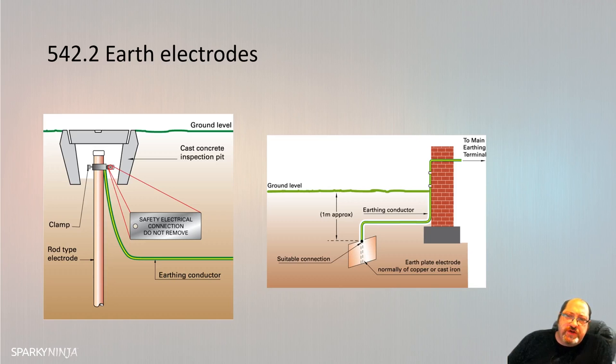With regards to earth electrode testing, if you're going to do an earth electrode resistance test when you install it, let's say now, this time of year, we're in a fairly dry spell, it's summertime, but if you were to install an electrode, you'd want to test it again in the polar opposite of the weather conditions, really. So dry, wet, frozen conditions.